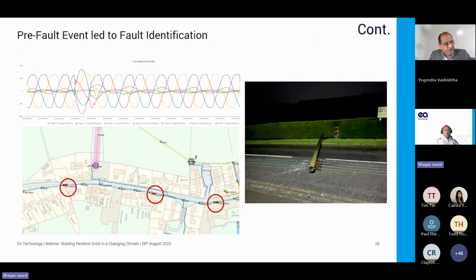So here is one example from this project. This case comes from January 2024 during Storm Isha that hit the UK, a widespread storm with high winds that impacted several regions. If you see this top left figure, a pole-mounted device on an LV overhead feeder recorded a waveform disturbance between L1 and L3 phases, indicative of either arcing, clashing, or insulation failure.